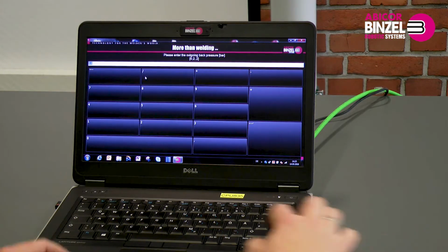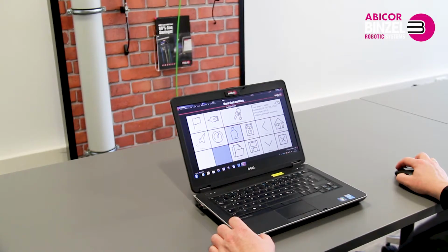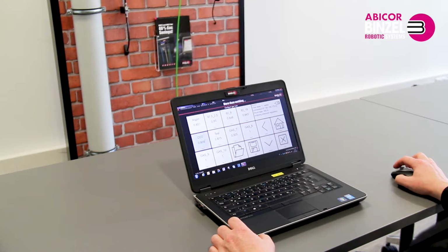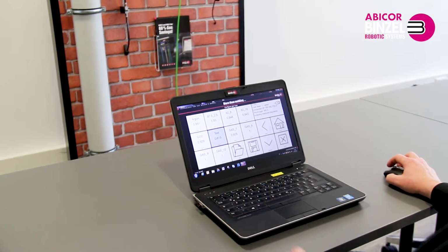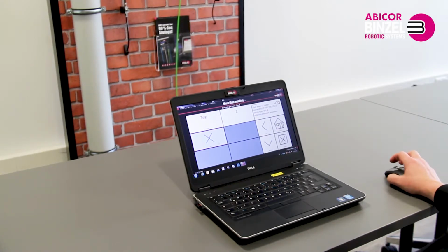With the service software, you can also configure the gas type. There are two special features with the service software. You can rename gases and switch them to visible or invisible. By making gases invisible, you will no longer see them in the device list. This feature is useful if you always use the same gas mix.